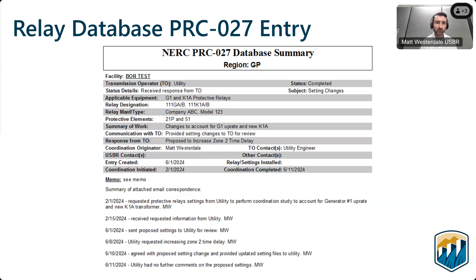The additional information this has includes some of the information-gathering phase as part of our relay setting development process. This shows that I reached out to the utility to ask for information on their protection systems and when I received that information. It also has all the examples I walked through previously of sending proposed settings to the utility for review, when I got a response, when everything was resolved, and when the coordination entry was closed out.